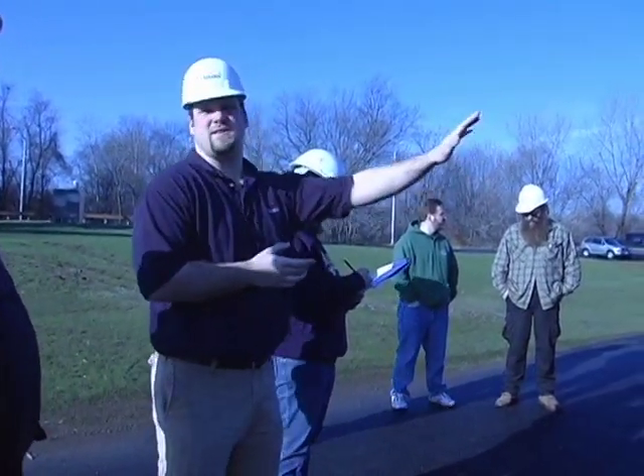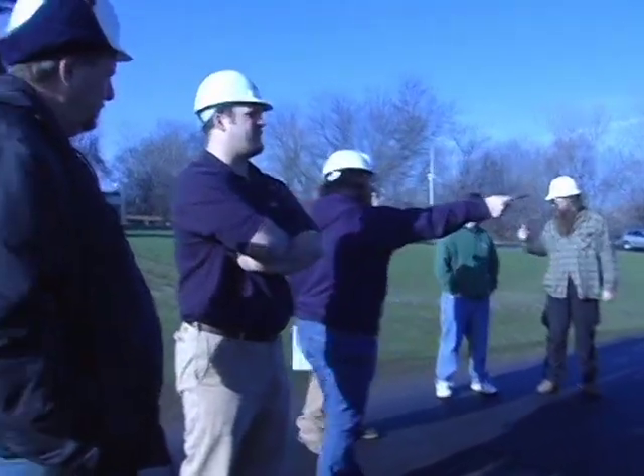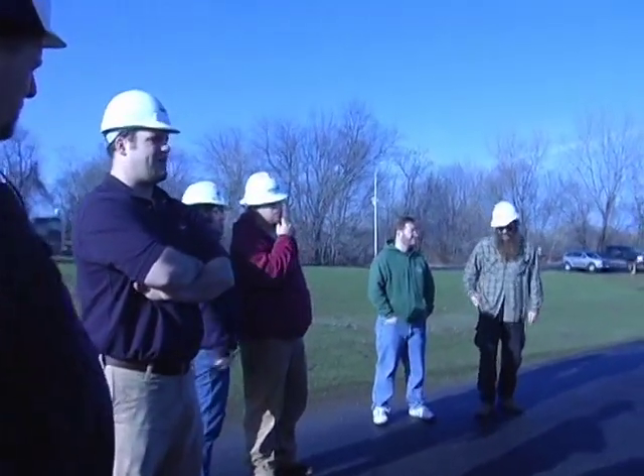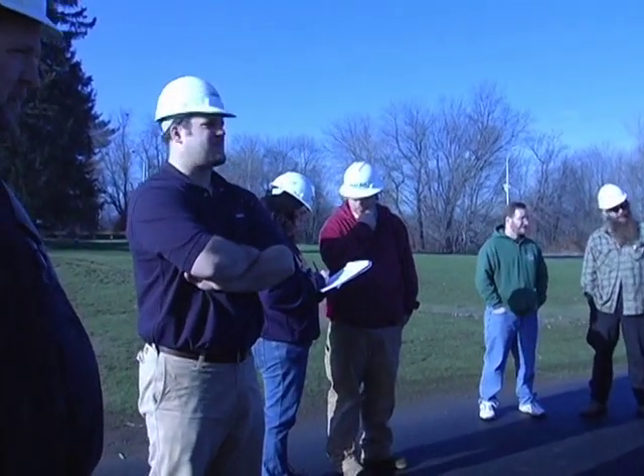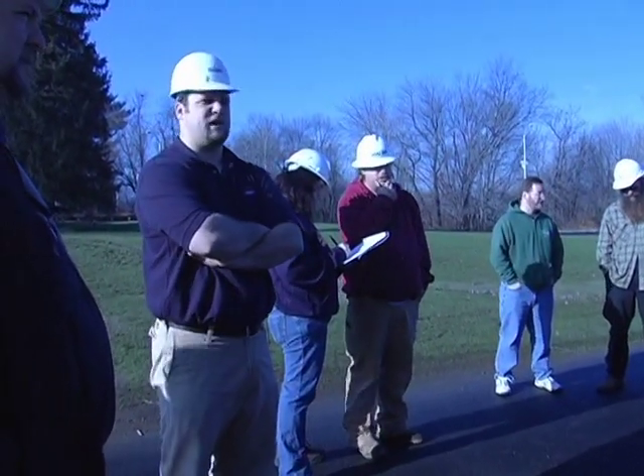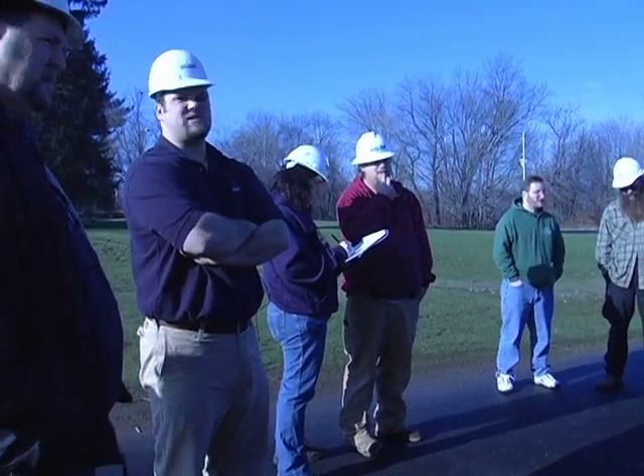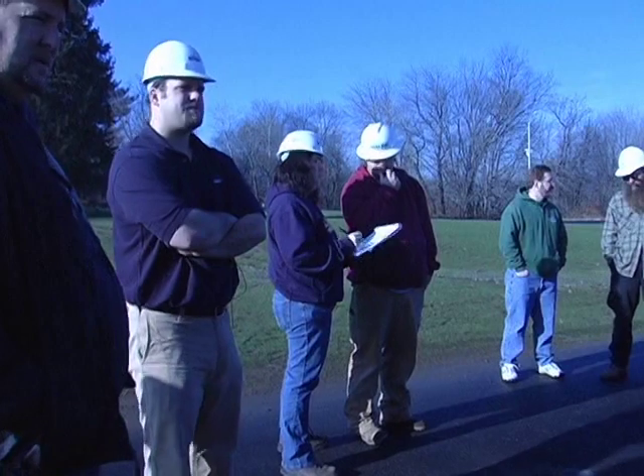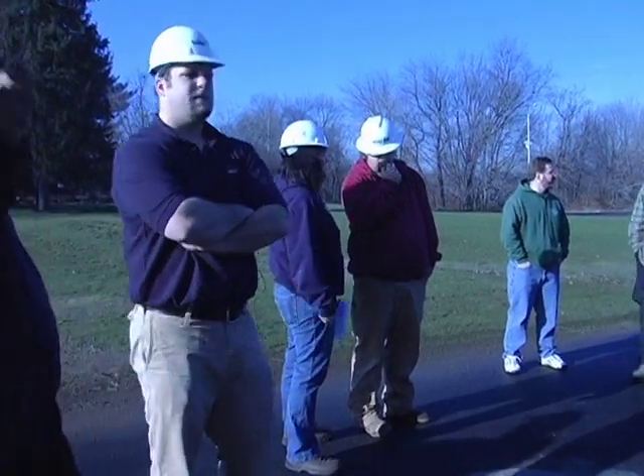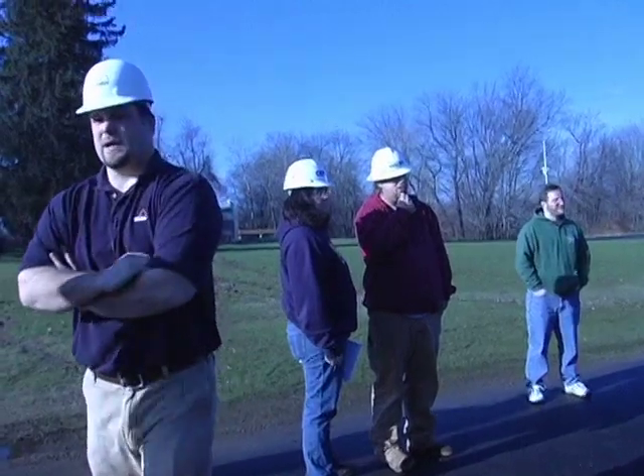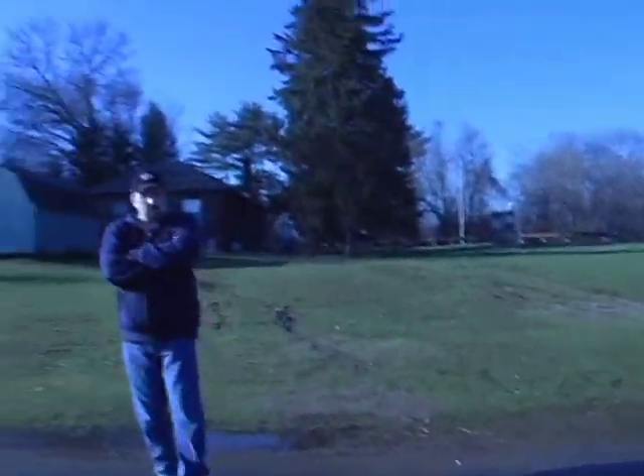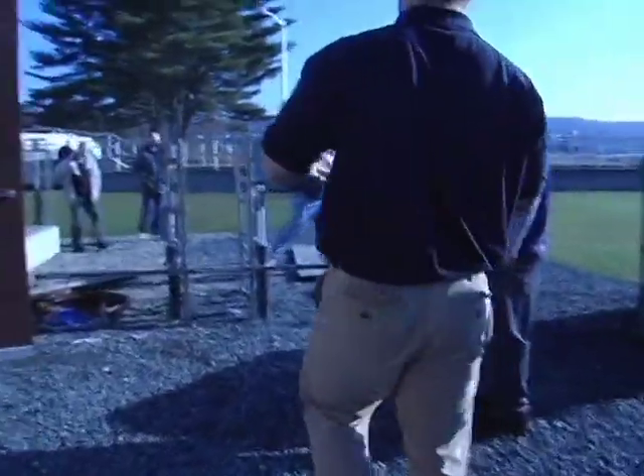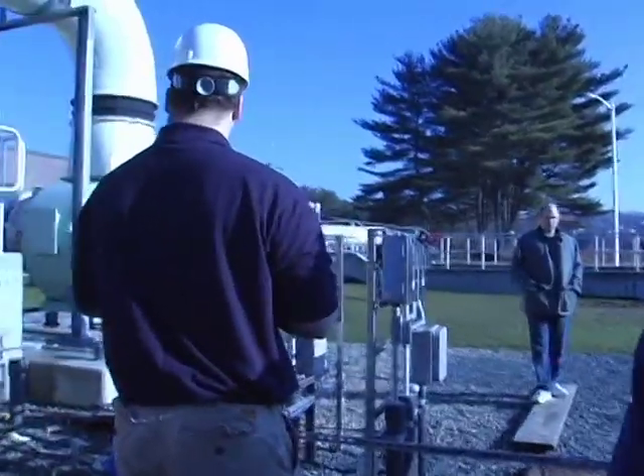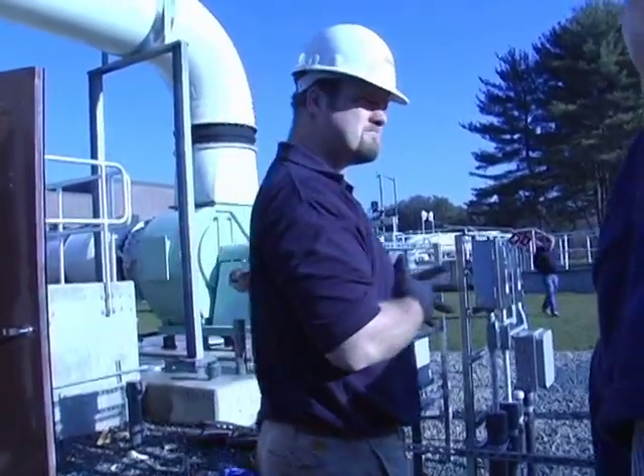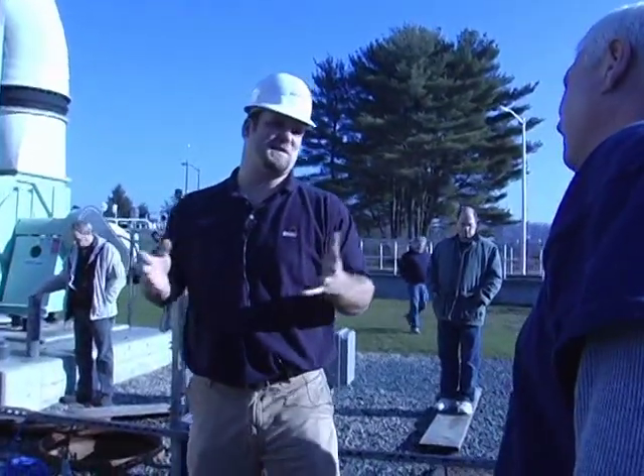Anytime you have to do any maintenance to the upper irrigation spray nozzles or anything underneath the covers, you have to ensure proper ventilation, whether that's in the form of taking covers off or a gas meter or something along those lines. Proper safety procedures should be taken. Is there a shut-off valve coming into the unit? There is. Over by the blower here, there's a main power on/off for the blower, and then there's also a damper there. There's no way you can even vent that thing if you still have gases coming into it. Exactly. That would defeat the purpose of venting it.